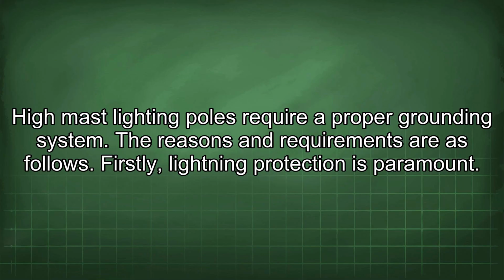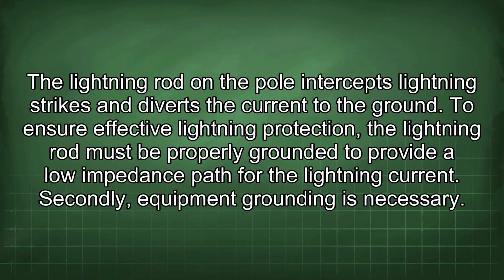High-mast lighting poles require a proper grounding system. The reasons and requirements are as follows. Firstly, lightning protection is paramount. The lightning rod on the pole intercepts lightning strikes and diverts the current to the ground. To ensure effective lightning protection, the lightning rod must be properly grounded to provide a low impedance path for the lightning current. Secondly, equipment grounding is necessary.